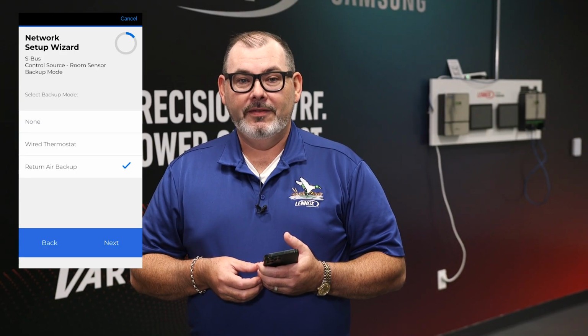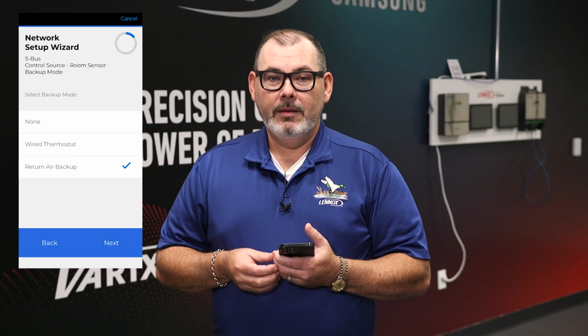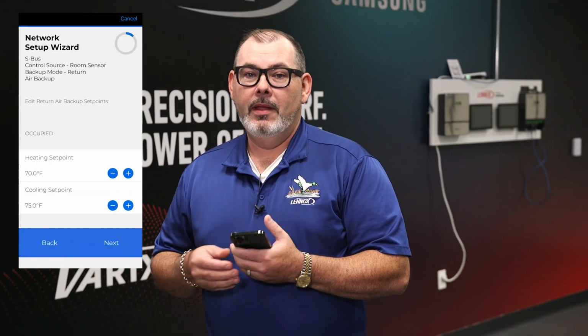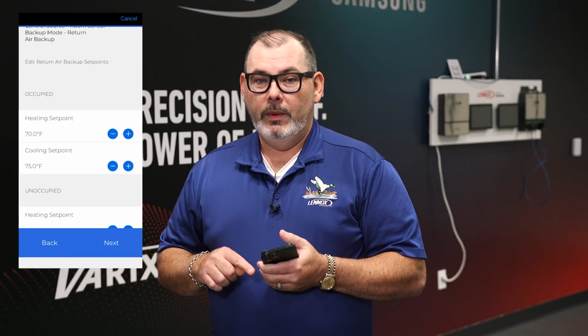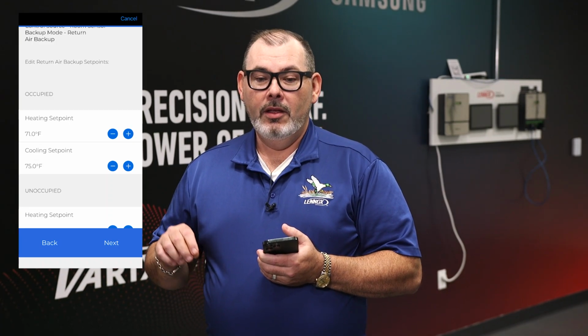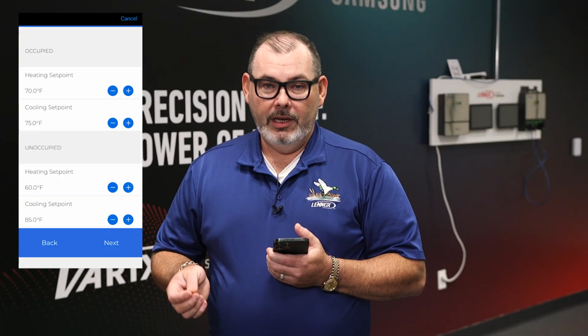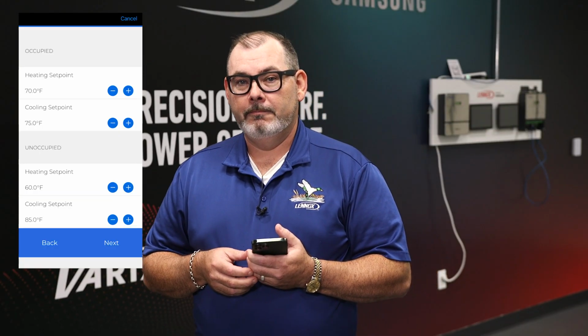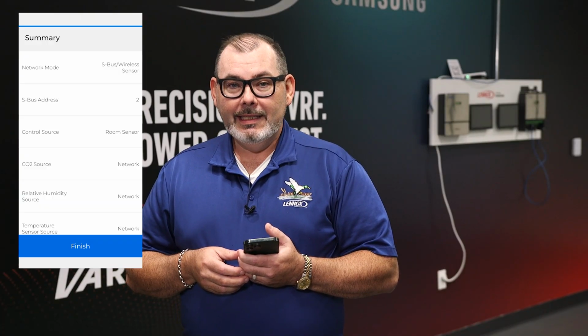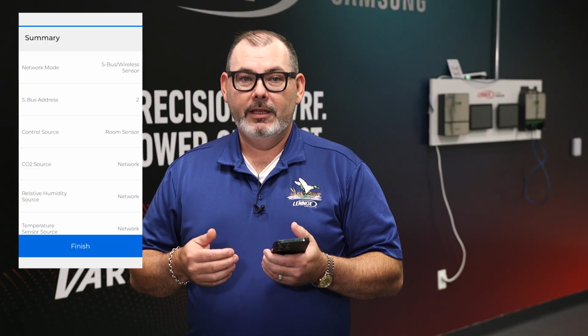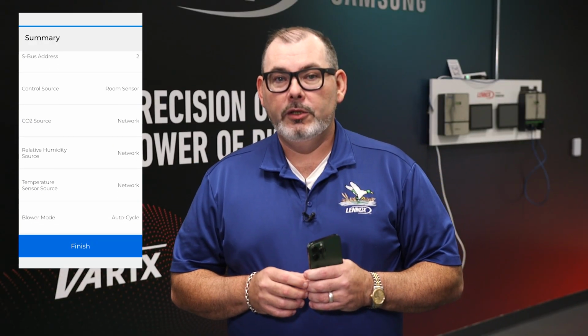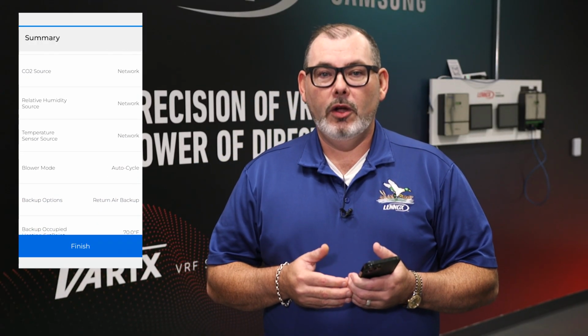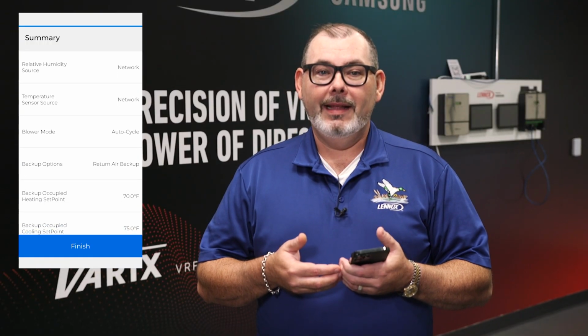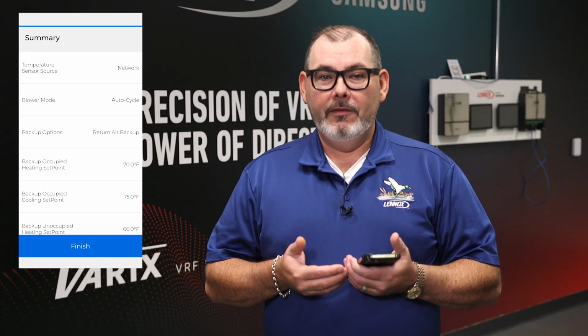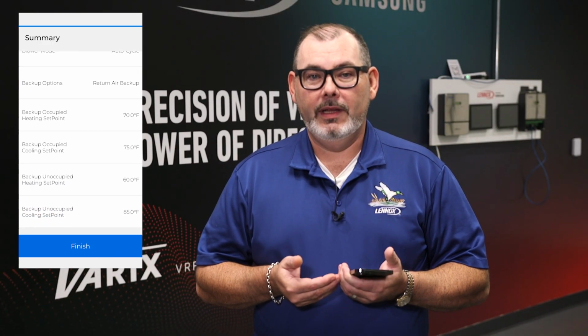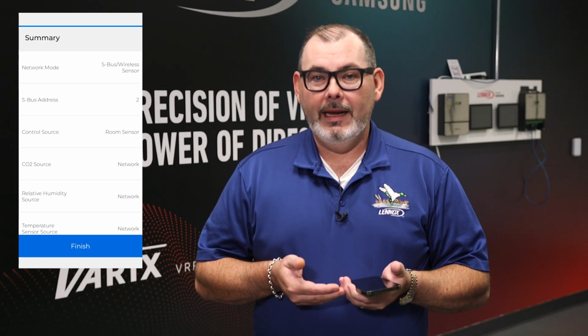After selecting the choice that best fits your needs, we will go to the heating set points for a return air backup. They need to be 3 degrees apart between heating and cooling. So if you've set it on 70 for heat, you need to set cooling to 75 or 73 and tap next. Once you've configured the controller the correct way, this will take you to the summary menu. Now that you've entered the summary menu, at this time, take a second to look over your selections. Make sure they're right. Verify that they fit your building needs. After you verified the selections, now you have successfully installed and paired to the 8500.